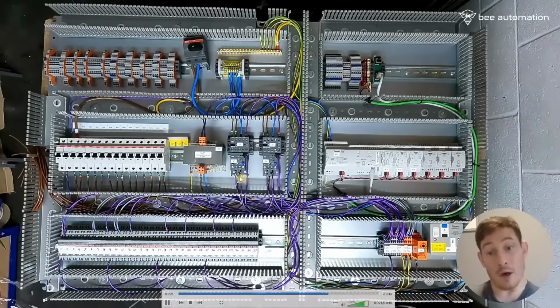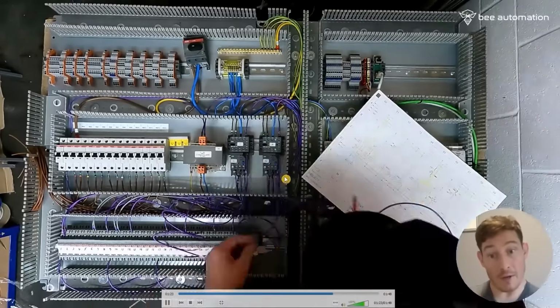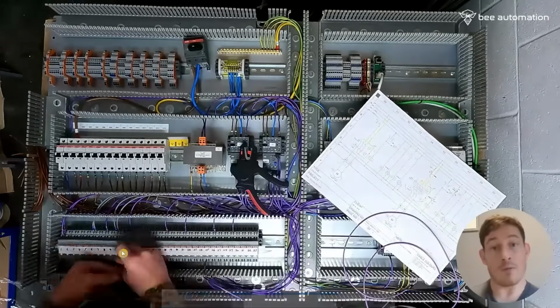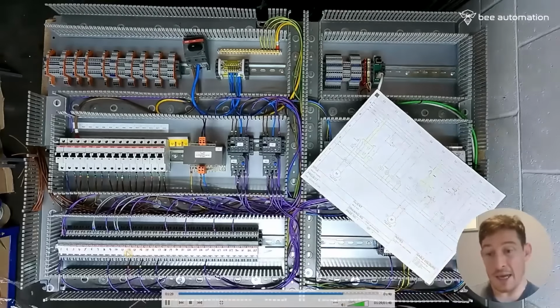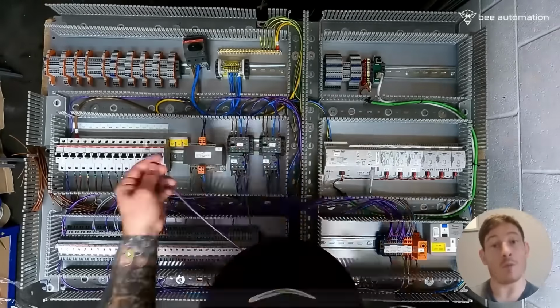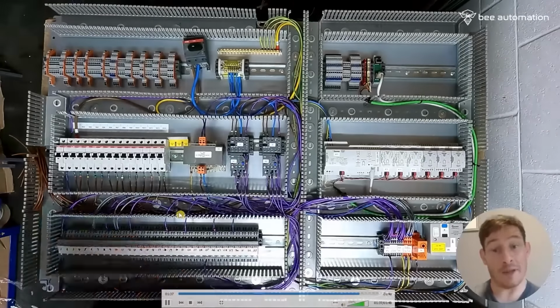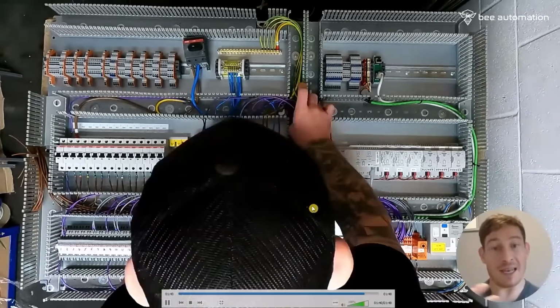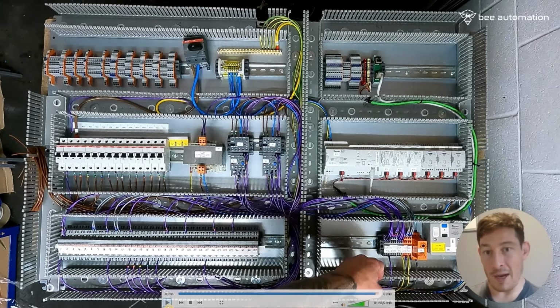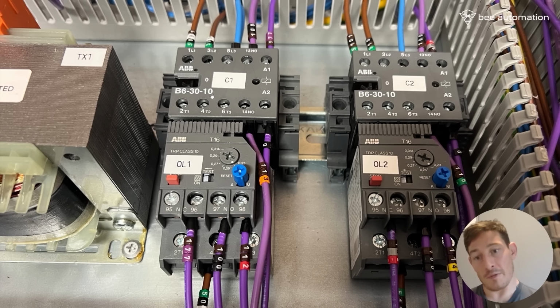And then on the normally open side of the contact on the overload, that will be going to a relay, energizing that relay, and then we've got 2-pole relays, so one will be going off to a light to say that it's tripped, and the other side will be going to the PLC to let us know remotely that it's tripped. Or we can program anything else we want off the back of that input. So yeah, quick overview from this image. Like I said, you've got the single phase coming in on L2, going out and then back around into L1. You've got neutral just on L3. This isn't wired yet because it's going off to the terminal blocks. That's something we do later.